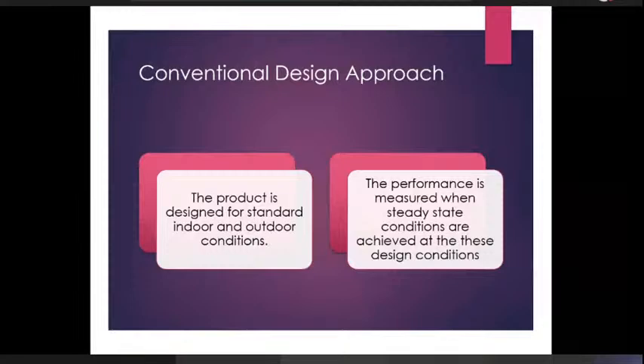So while the market at that time was on 1.5 ton or 18,000 BTU per hour and energy efficiency expressed as BTU per hour per watt, we agreed on a dimensionless number as per the international standard. We looked at a dimensionless number and we defined bands of EER that would be put on the product. And we also had to define the test method. So what test method would be used so that there is no element of doubt. Manufacturer tests at his labs and then it goes to another lab and there's a difference and all that. And there could be a lot of controversy around numbers.